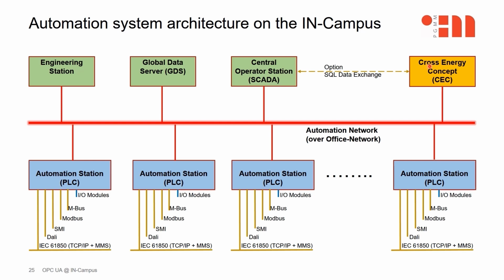In addition, the cross-energy concept has the possibility to access the SQL database of the SCADA system and thus to obtain historical data that can be important for forecasting and optimization. The automation stations themselves do not exchange data directly with each other, but report their needs to the global data server, which in turn provides the desired information to them. This concept ensures that any impact on the system can be easily traced during maintenance or modification work.